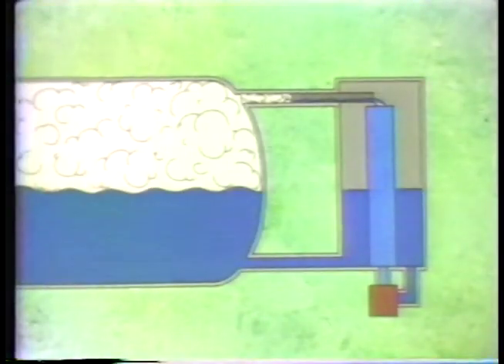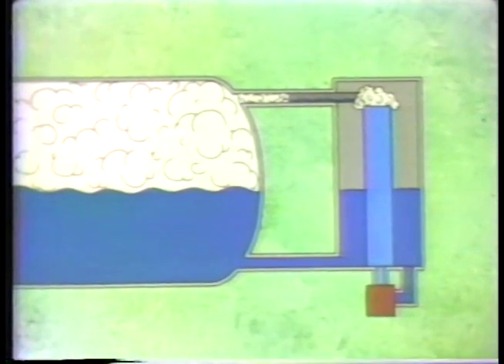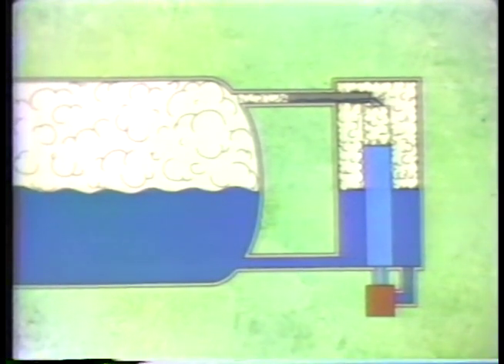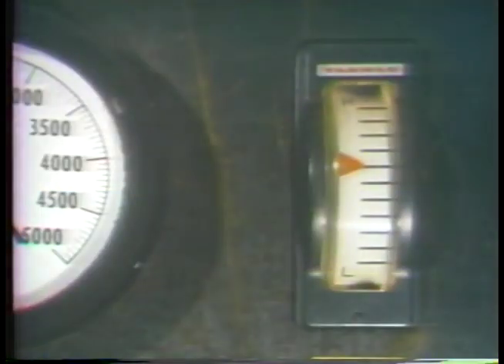The temperature of the water in the reference leg is normally lower than the saturation temperature for the boiler pressure. If the boiler pressure suddenly drops very low, the temperature of the reference leg may be greater than the saturation temperature for the new, lower pressure. This means that the water in the reference leg is hot enough to boil, and it will begin to flash to steam. As the water boils off, the level in the reference leg decreases, reducing the differential pressure between the two legs. The result is that even though there has been no actual change in water level in the boiler drum, the level indicator shows an increase in level due to the decrease in differential pressure.